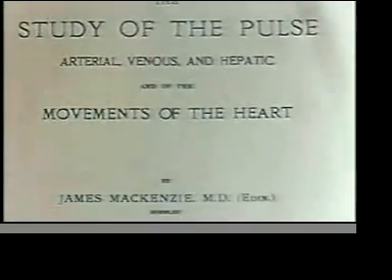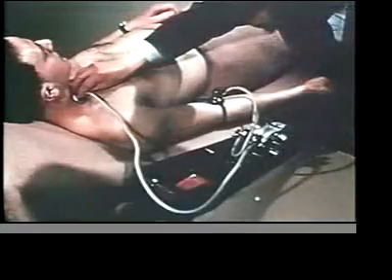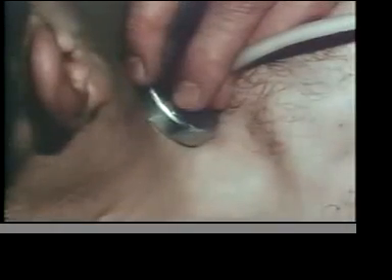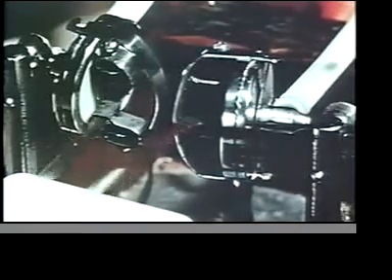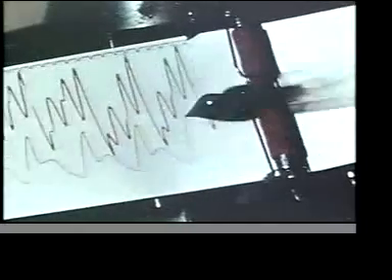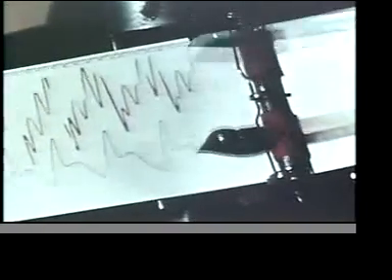His investigations were made chiefly by means of the clinical polygraph. A cup-shaped receiver was placed over the pulsating vein and connected pneumatically by way of a rubber tube to a tambour. To the membrane of this, a lever was attached. In Mackenzie's original instrument, the lever marked smoked paper covering a revolving drum, but in this instrument, modified by Sir Thomas Lewis, the lever carries a pen which writes on smooth white paper. The polygraph has several drawbacks, including time lag due to air transmission, overshooting due to the mechanical inertia of amplifying levers, and the primitive method of recording.